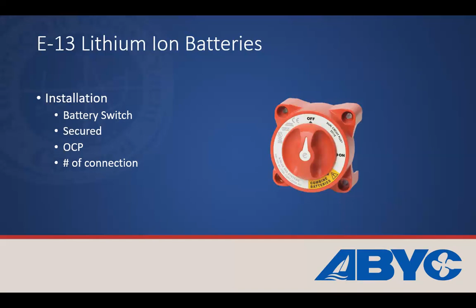Again, common number of connections, just like any battery, we want to make sure we don't exceed more than 4 terminals on any post or connection. So we talked about this. The standard also has an appendix that talks about thermal runaway. And you can see here a chart that shows a couple of different scenarios on how you could get to thermal runaway.